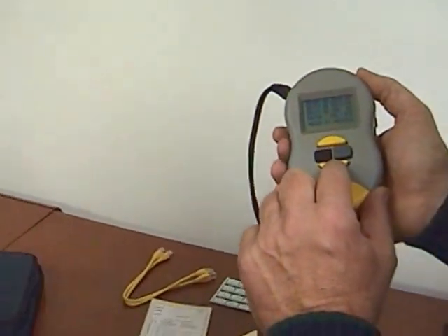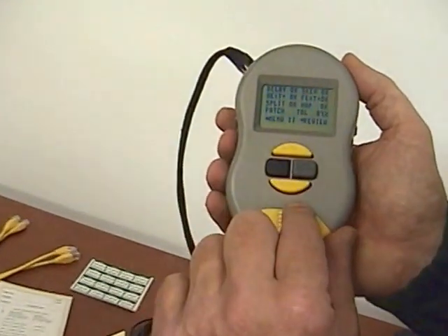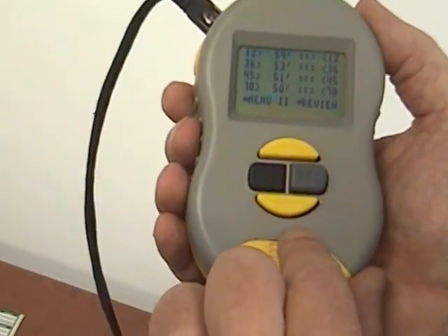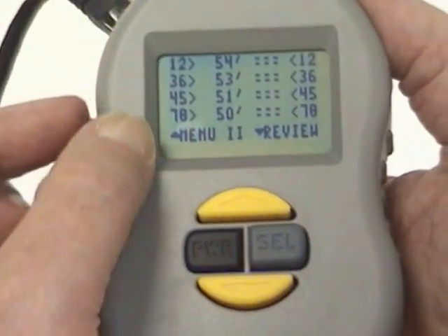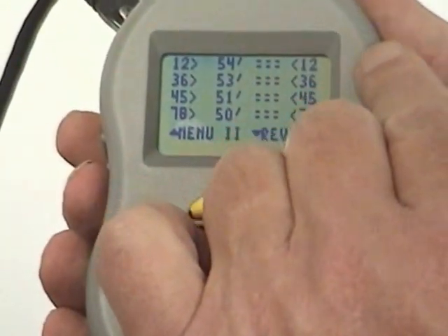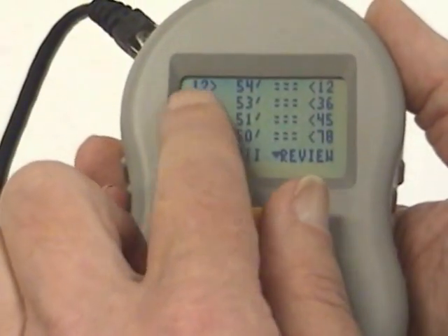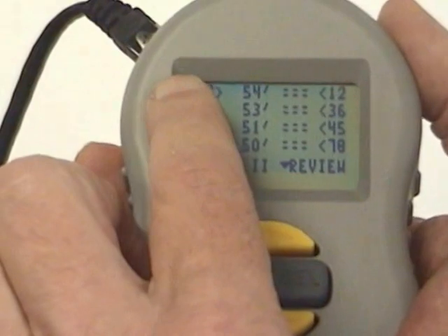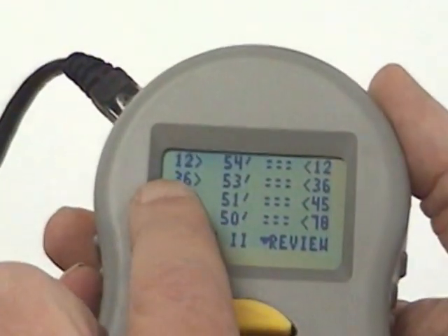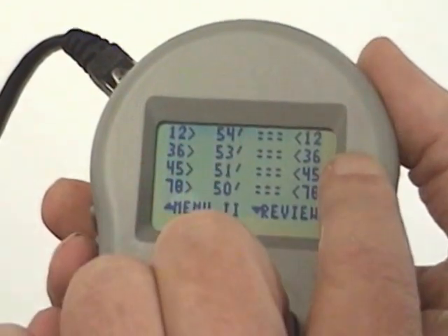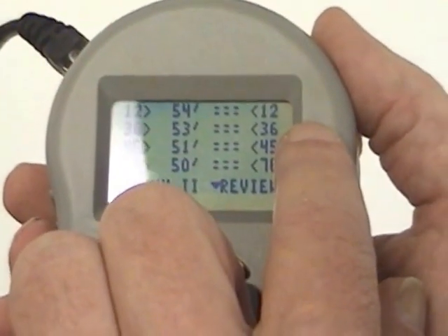That's right, Daryl. And now we continue with our review, and we can see the map. The map tells us where the pairs on the near end connect to the pairs on the far end. In this case, we see that pair 1, 2, in other words, pin 1, 2 is connected to 1, 2 on the far side. 3, 6 on the near side is connected to 3, 6 on the far side.